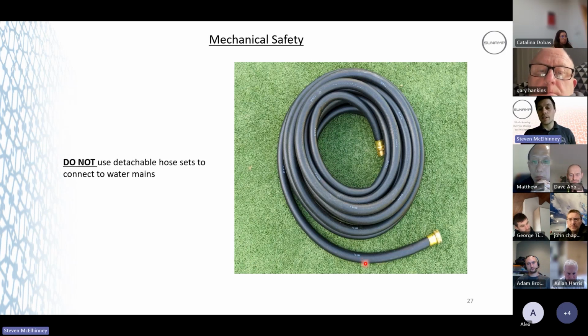So the braided hoses, they can burst, they can kink. If you're running water through them all the time, you can get the little rubbery inside part of the pipework coming through. So we do recommend using rigid pipework on the heat battery itself. It can be quite tight, because the reason I'm saying this is we have had some jobs where installers have fitted a battery under a kitchen unit, and they've used detachable hoses to then pull the battery forward if they've ever had to work on it for any reason, like a gas cooker hose or something. So we don't advise that. Rigid copper into the unit.